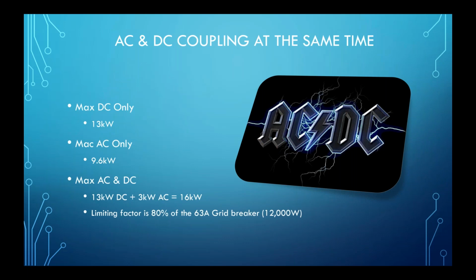If you don't have an existing solar system and you don't have an existing inverter, then you don't need to AC couple at all. You just get your solar system and figure out whether it's roof mounted or ground mounted or however you want to design it, bring that PV directly into the Sol-Ark. The maximum amount of PV that you can bring into the Sol-Ark from DC, straight from the photovoltaic system, is 13 kilowatts. The maximum amount, and this is a Sol-Ark 12K statement again, that you can bring in AC is 9.6 kilowatts.